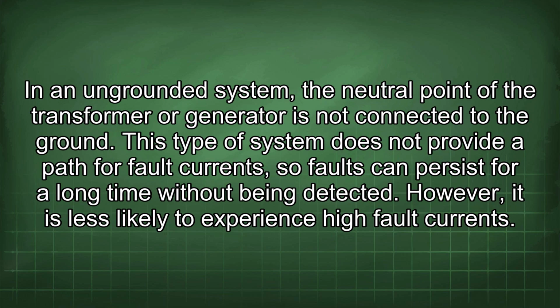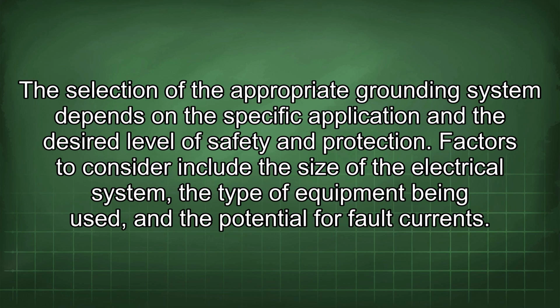In an ungrounded system, the neutral point of the transformer or generator is not connected to the ground. This type of system does not provide a path for fault currents, so faults can persist for a long time without being detected. However, it is less likely to experience high fault currents. The selection of the appropriate grounding system depends on the specific application and the desired level of safety and protection.